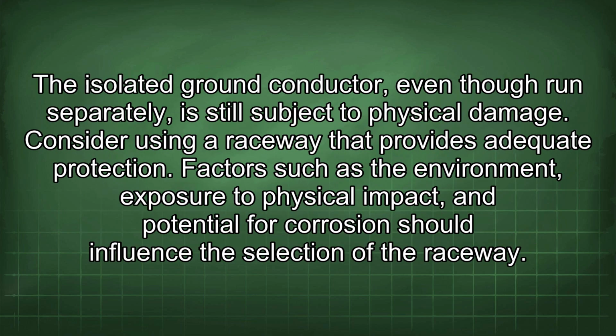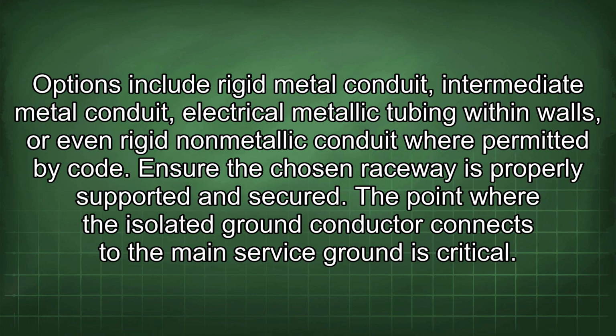The isolated ground conductor, even though run separately, is still subject to physical damage. Consider using a raceway that provides adequate protection. Factors such as the environment, exposure to physical impact, and potential for corrosion should influence the selection of the raceway. Options include rigid metal conduit, intermediate metal conduit, electrical metallic tubing within walls, or even rigid non-metallic conduit where permitted by code. Ensure the chosen raceway is properly supported and secured.